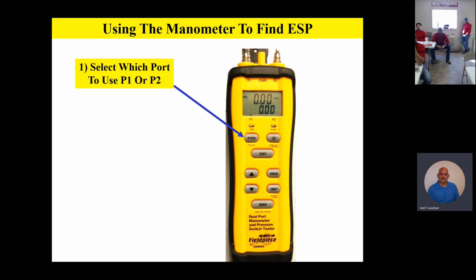And I recommend you just use one port, by the way, and we'll show you why in a second. Some people like to use both ports and take supply and return static at the same time. I like taking them separately and adding them together, because I think you get a better reading. It's more stable. Let's think about it: if I had a turbulent air source on the supply and a turbulent air source on the return, now I'm trying to find the pressure between two turbulent sources. However, if I take them individually, referencing one side to the atmosphere and the other side to the static pressure, and then add them up, you actually get a better reading, in my opinion. So I just like to use one port.